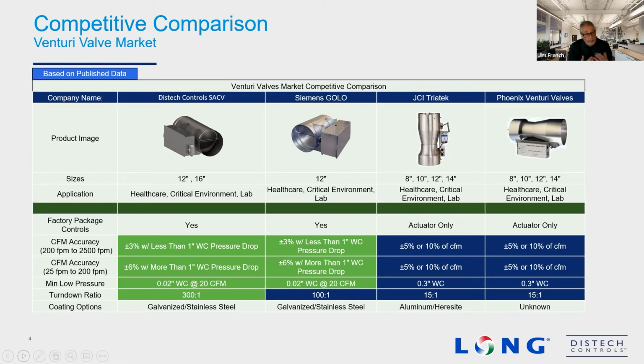meet that requirement. The SACV is an ASHRAE 195 compliant device because it does come factory tested, complete, commissioned, pre-balanced as a unit right out of the factory. And so that is an advantage to this. It simplifies the install and the startup of the mechanical system in general. As you can see here, we're achieving a lot less inlet pressure than traditional systems. In this chart, we compare to Venturi valves or the Triatek. We even have the new Siemens GOLO in comparison on this chart.